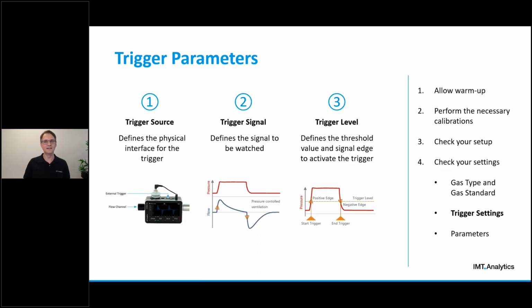Then the trigger signal defines which signal shall be used for triggering. Here you can typically choose between the pressure and the flow signal. For example, if you have an analyzer that measures the pressure inside the flow channel and you want to use that signal for your triggering, then you would select the flow channel as trigger source, and then the pressure measurement inside the flow channel as your trigger signal. Finally, the trigger level defines the threshold value of the trigger to be activated. In addition to the threshold level itself, you will also need to define whether the trigger shall be activated when this threshold is reached on a rising or a falling edge of the trigger signal.